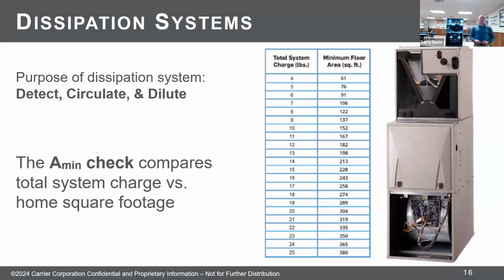Now, what does that mean? Because of that, how much refrigerant per square foot is how it's being calculated. You're going to see this chart in the outdoor units that have the new 454B refrigerant. What the chart is telling you is that if you have so much refrigerant in your system, you need so many square feet of minimum floor area to dissipate that refrigerant to a safe level. That's called the A minimum check.